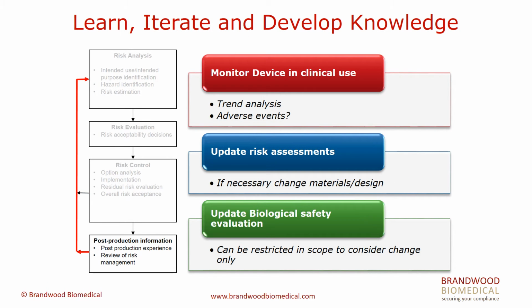And then the final step, of course, in risk management is that it's a living process, and you learn from post-production information, from placing the device in the field, in the clinic, and we learn. Monitor the device in clinical use, see what trend analyses we have. Are we seeing adverse events relating to biological safety? If necessary, we may need to update our risk assessments or change the device. And in doing so, repeat the biological safety evaluation.